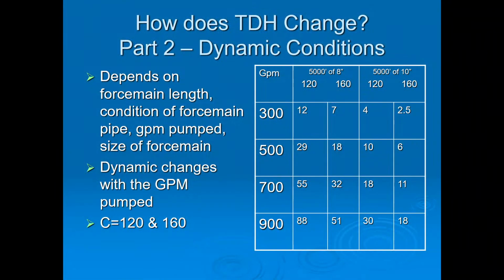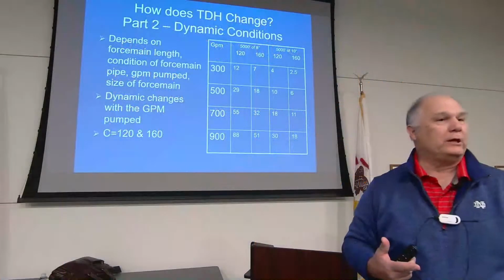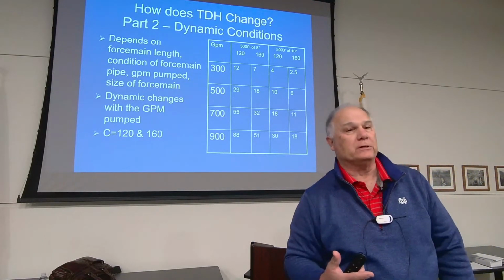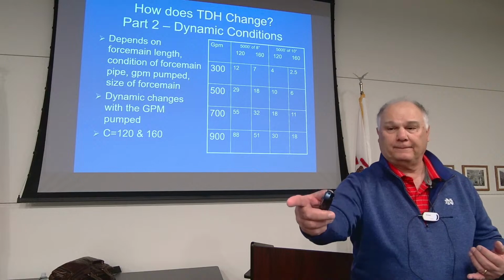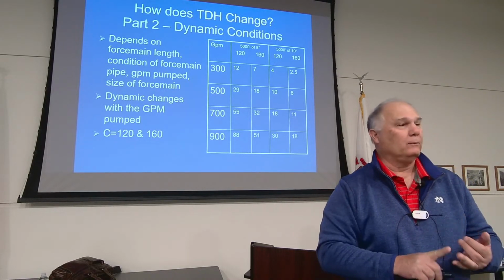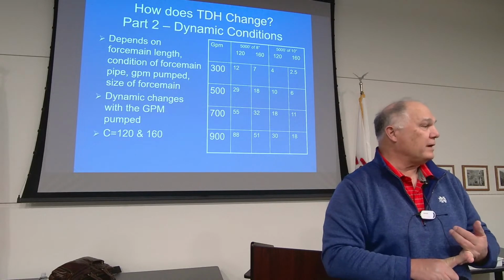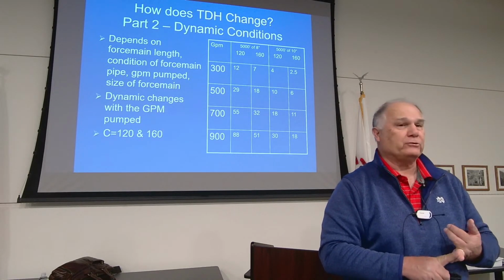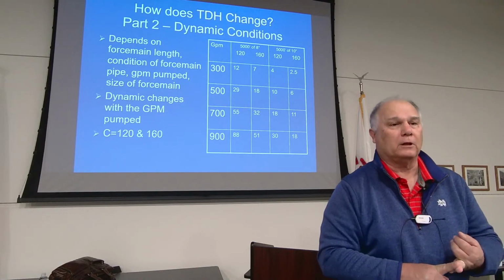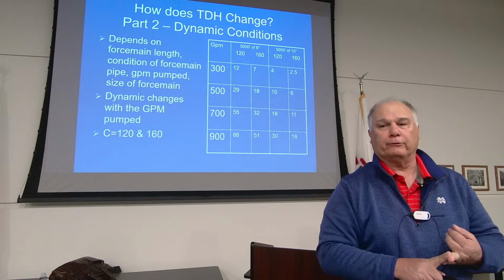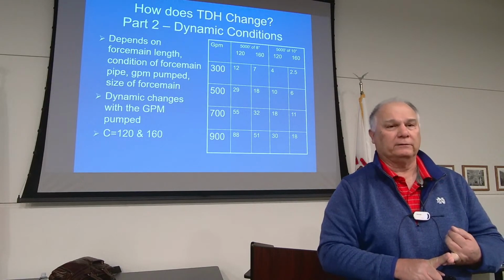So as we look at examples, this particular one is a dynamic curve. Why is it dynamic? Anybody know? Why do we call it dynamic? It's dynamic because it can always change. What can change in that system? The things that can change are the amount of gallons we're pumping. What else? The condition or the type of pipe in the ground. So say, for example, we're pumping through an old cast iron, ductile iron pipe that's been in the ground for 100 years. What's that thing going to look like?